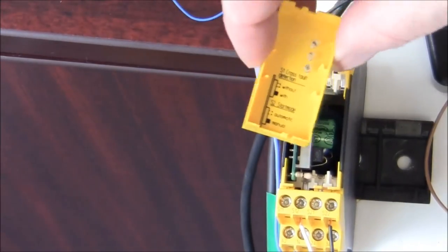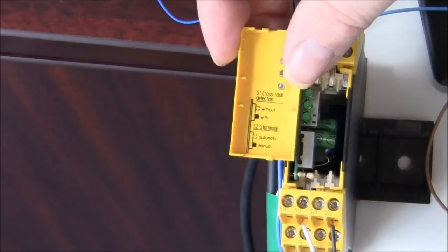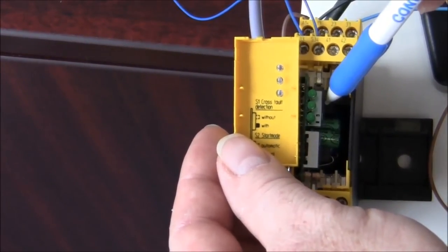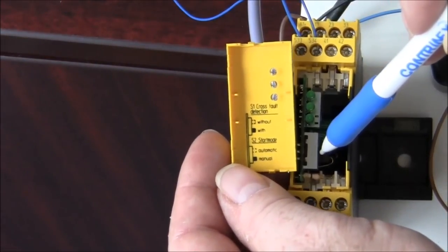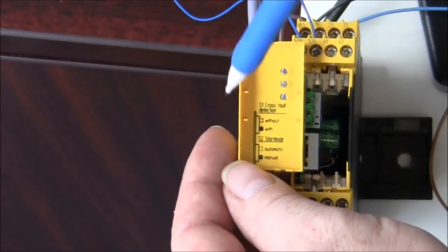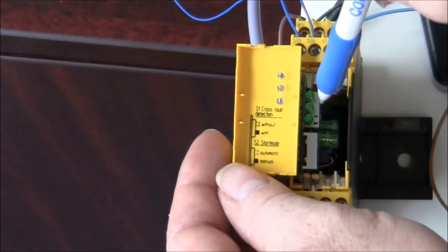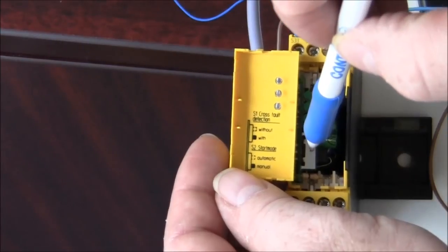On the reverse side of this panel, it will show you the positions of S1, which is right here, and S2 right here. I don't know if you can read it, but this says automatic or manual position, without or with. And the drawings show that in both cases, this goes to without, and this is the only one that you change. So for manual mode, we switch that down to manual.